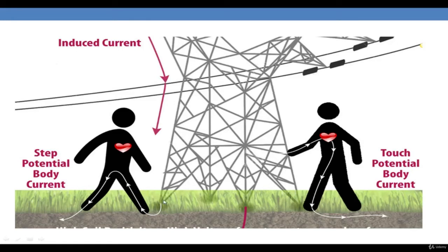Whereas in the case of step potential, the induced current flows from the tower to the person's feet. Because these 2 feet are at different positions or different points, the potential difference will cause a current to flow through the legs of the person. So as you can see, the touch potential is much more severe than the step potential, because the path of the current is through the heart in the touch potential, whereas in the step potential the current path is only through the legs.